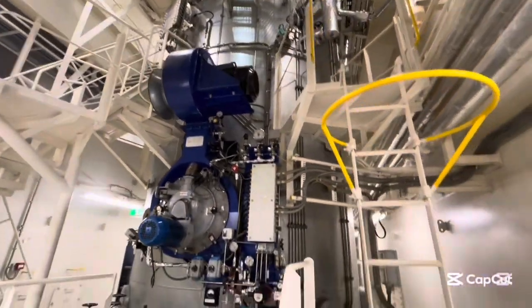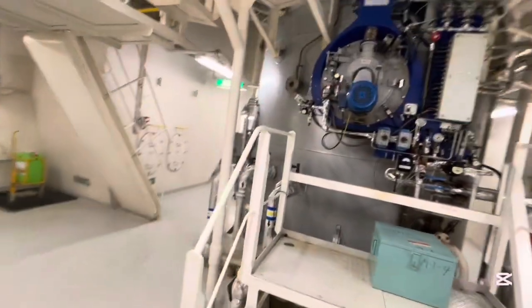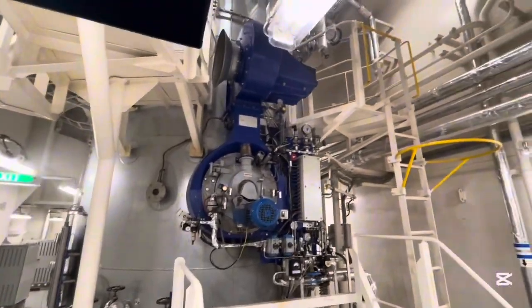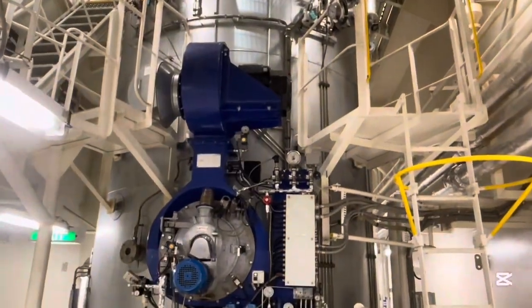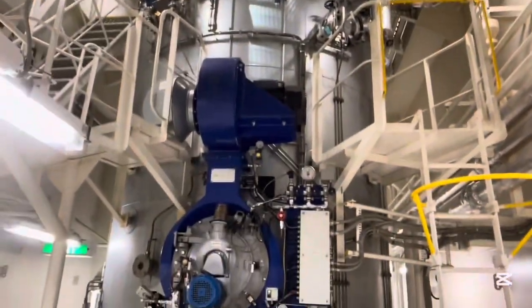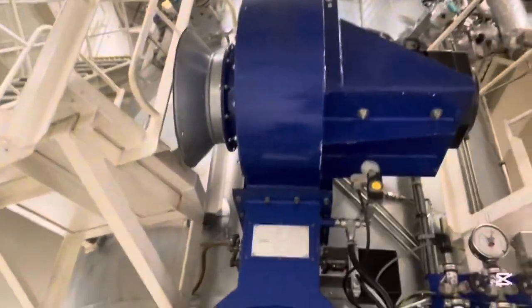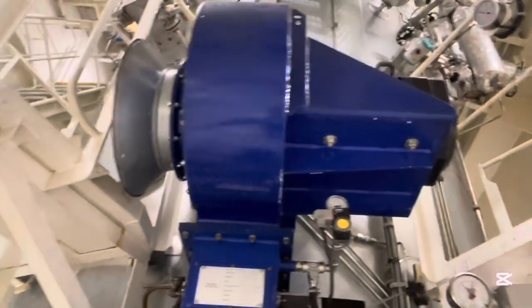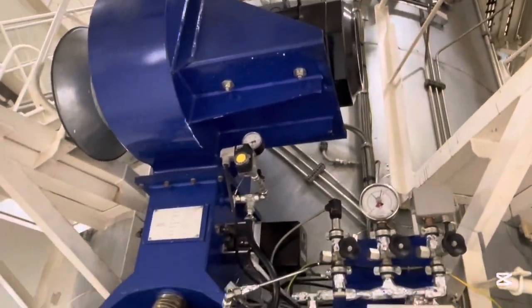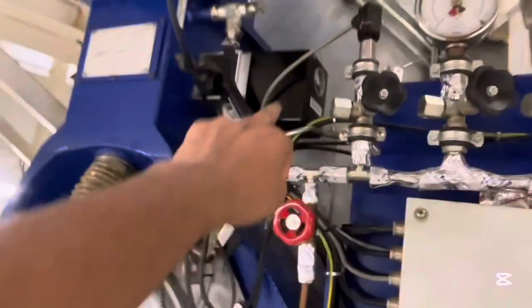So basically this is the boiler, and the blue color part on this metallic structure, even the blue is a metallic part, but on that silver, the blue part is the burner. That whole complete blue color set is the rotary cup burner set. And on the top you are seeing the combustion air fan motor, which sucks the air. For ignition we need air, fuel and heat, and as a part of it, the one which is responsible for air is that particular motor.